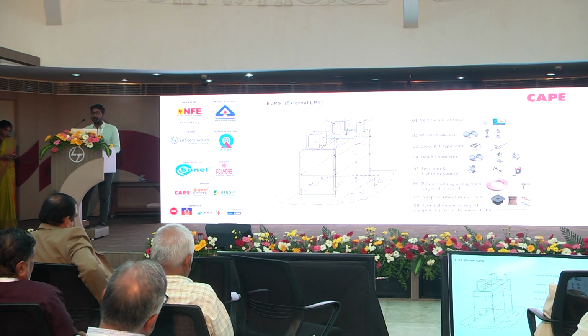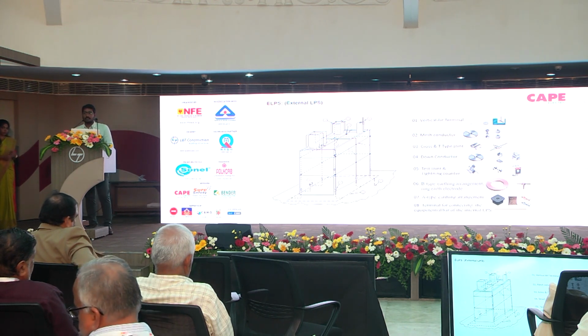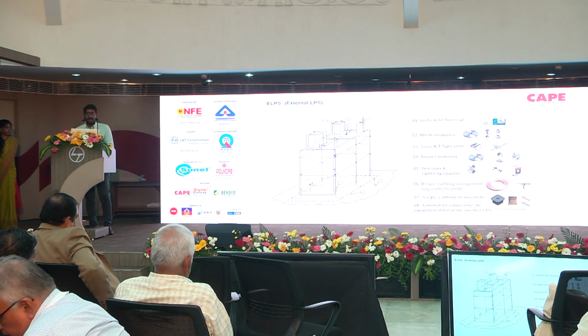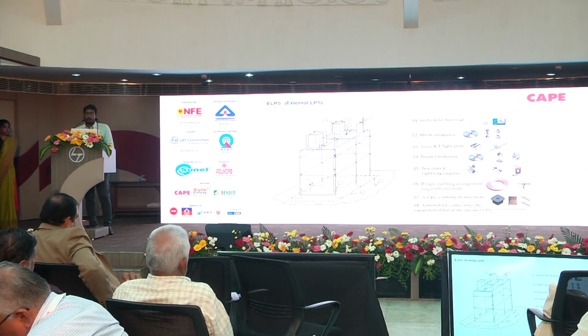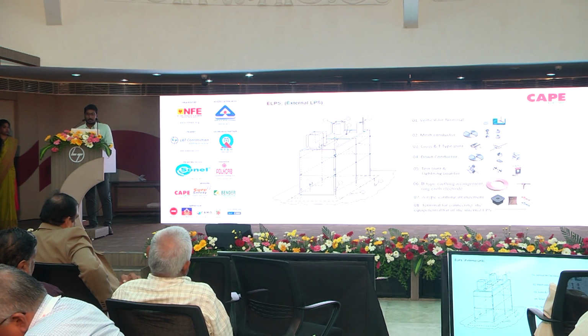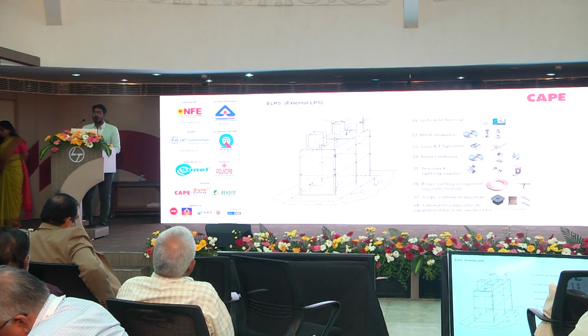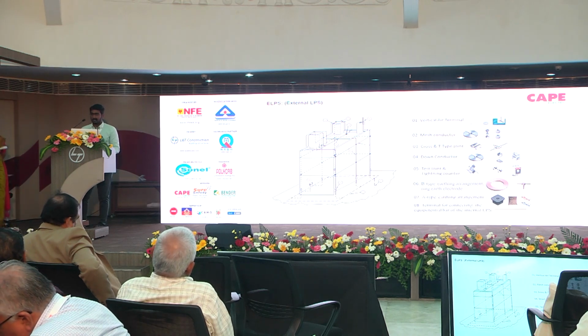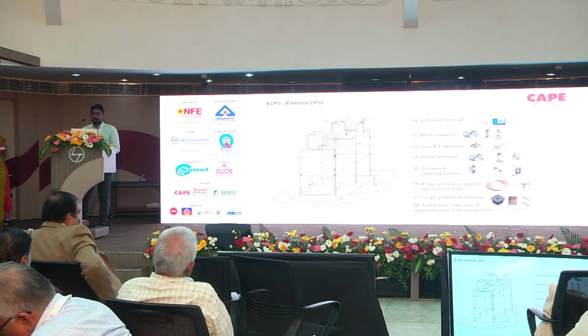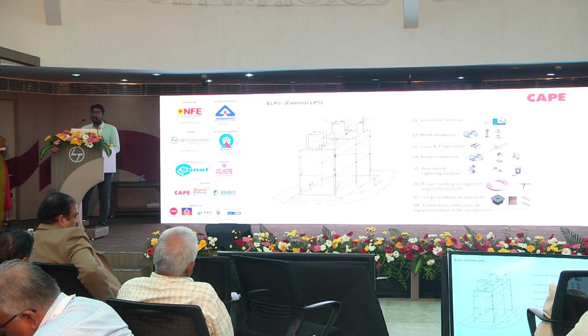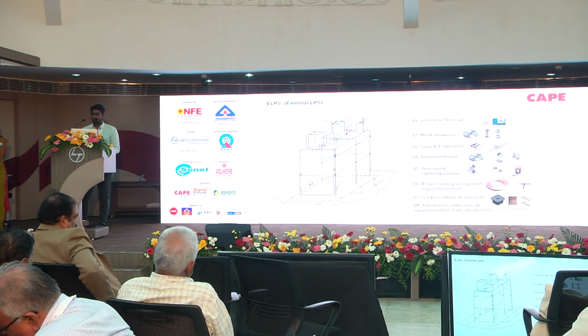For type B earthing, we are recommending a copper bonded conductor of 10 mm size, which will be laid around the building, and all the down connectors will be interconnected with this 10 mm copper bonded conductor via exothermic welding. We suggest exothermic welding because it gives a strong bond, and it will act as a single conductor with continuity resistance. And the type A arrangement is nothing but each down conductor having an individual earth electrode. And the accessories are a copper bonded earth electrode with clamping, a chamber and chemical compounds, which are termed as ProCell.